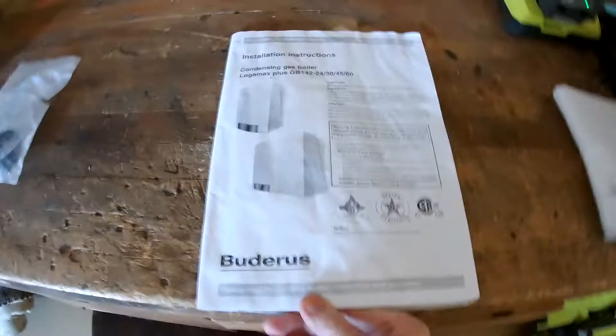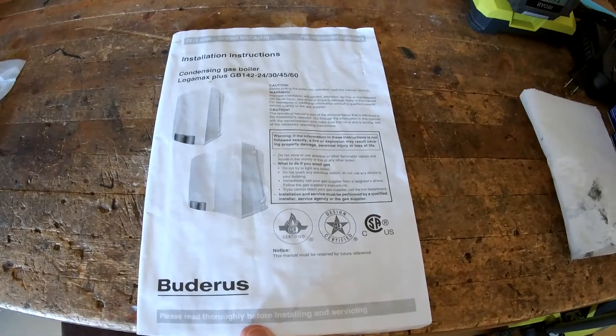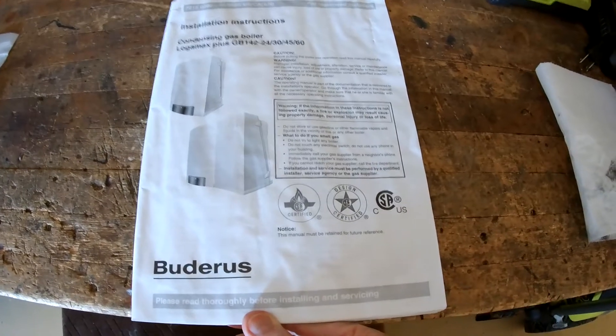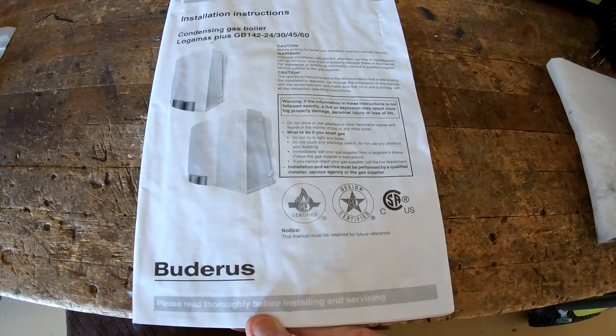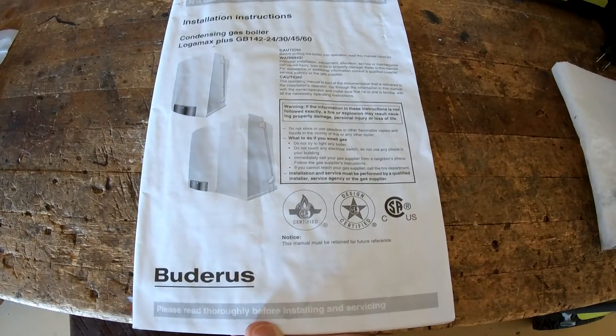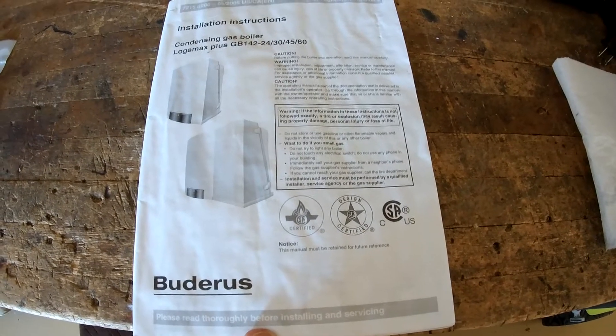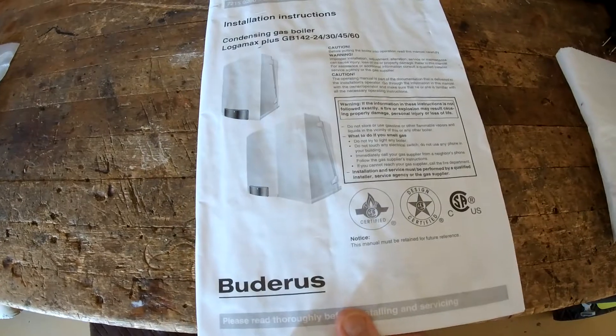So the service code 3C with error code 217 basically has to do with the fan. And this is the installation instructions that I was able to keep when the installer left. I've got the GB142 Model 30. I think the 24, 30, 45, and 60 are relatively the same, just different sizes of capacity.